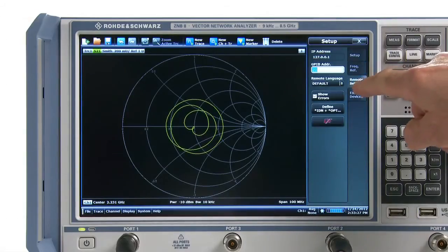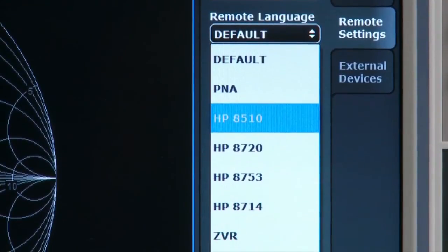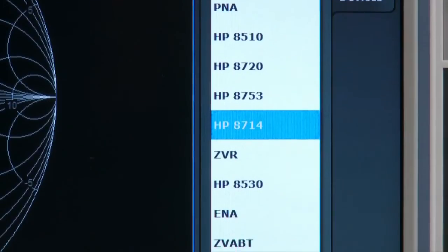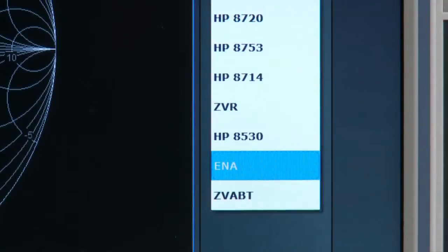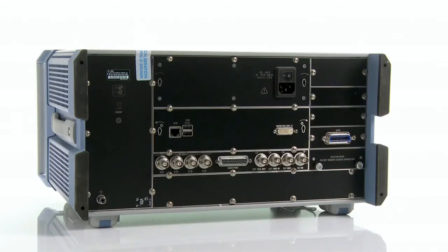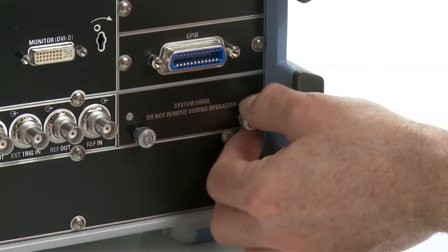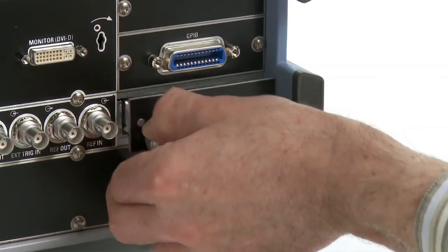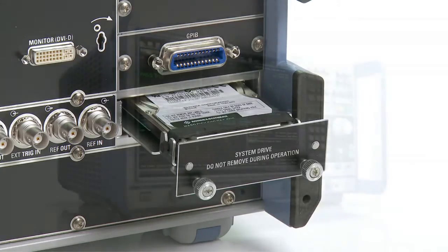The ZNB is to replace an obsolete analyzer in an automatic test system. Nothing could be simpler. All you need to do is select the previous instrument's remote control command set from a list. The ZNB has a modular hardware design, so it will keep up with technological developments for a long time to come. The controller, control interfaces, power supply and hard drive are designed as plug-in modules for convenient replacement. This also makes it easy to accommodate new technologies and performance enhancements.